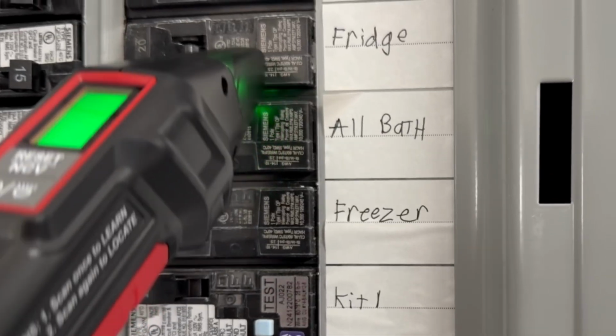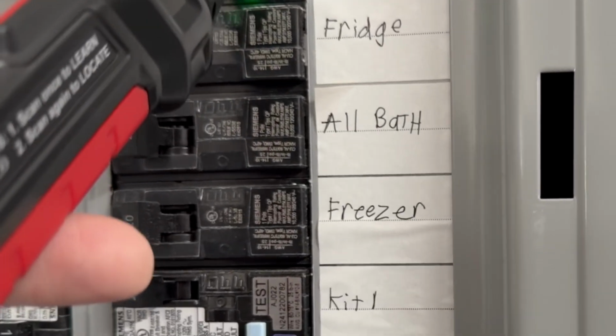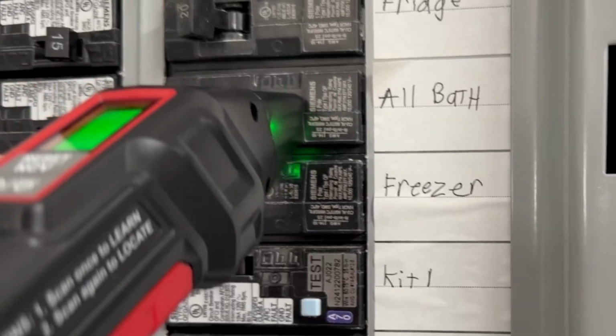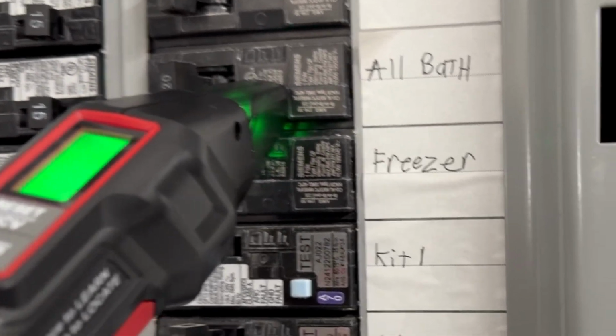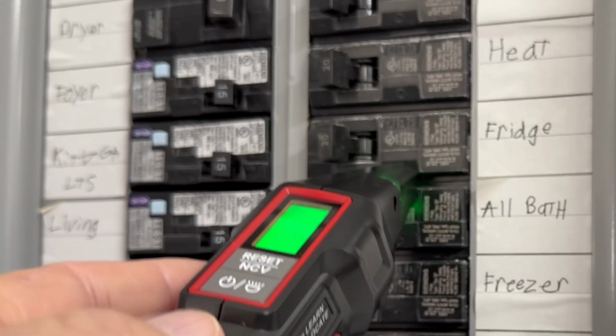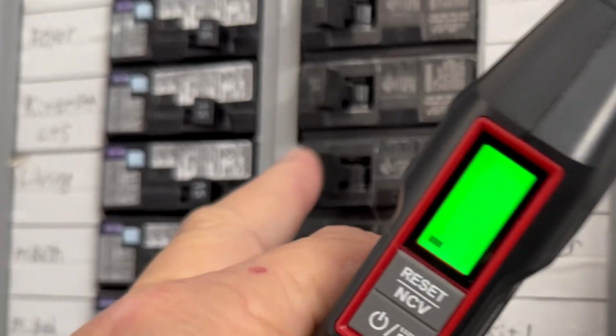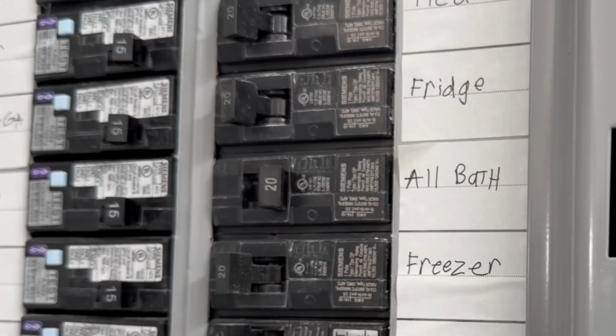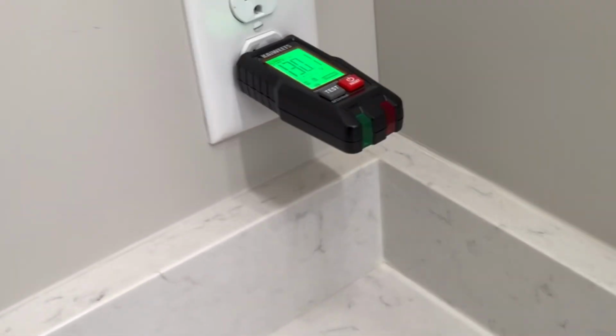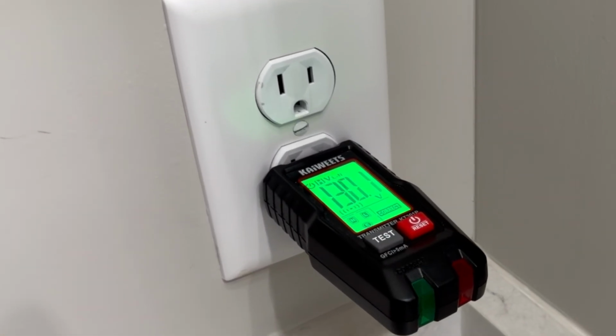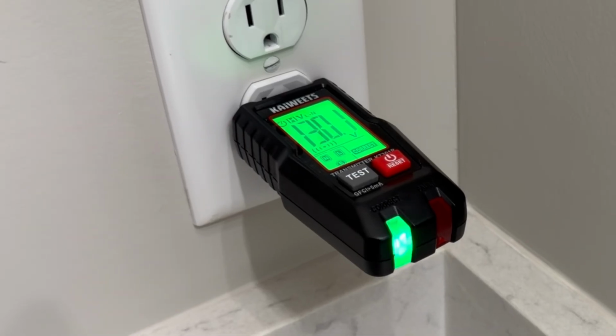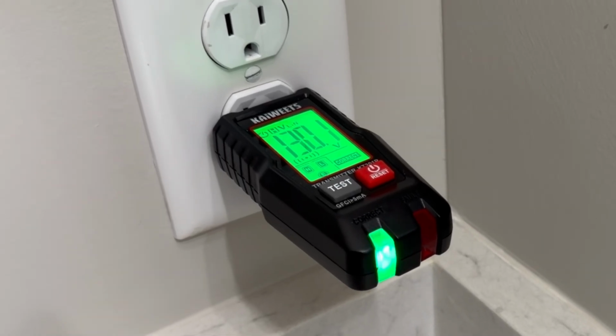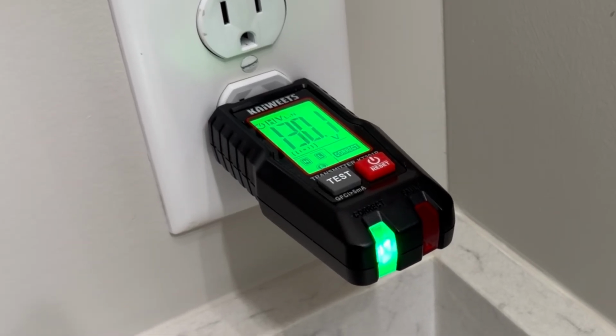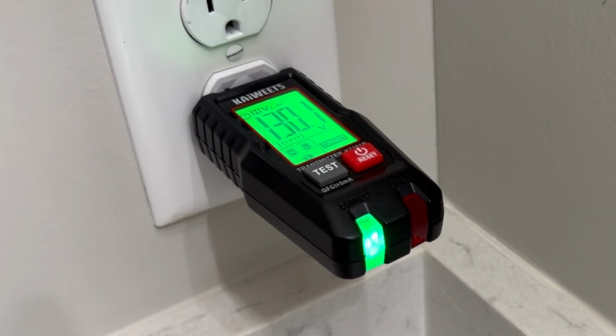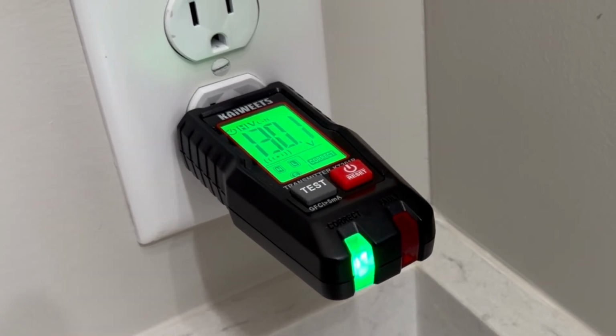So the one that's labeled all bath is beeping. It's not strong. There it is. So let's turn off the one that's labeled all bath, and let's see what the transmitter says. Okay, looking at the transmitter, you see the green light is blinking. That means there's no voltage flowing through the transmitter, so we did isolate the correct breaker in the panel.